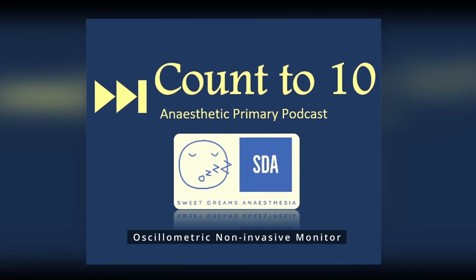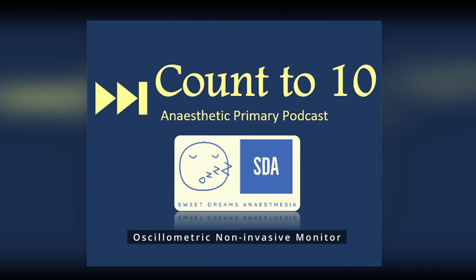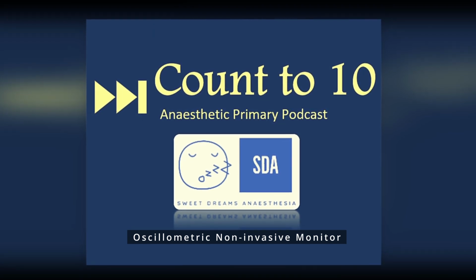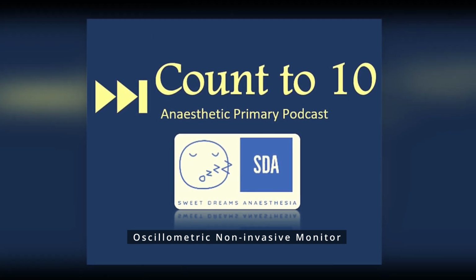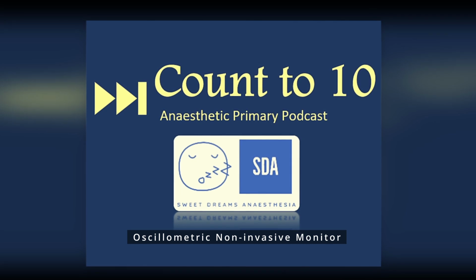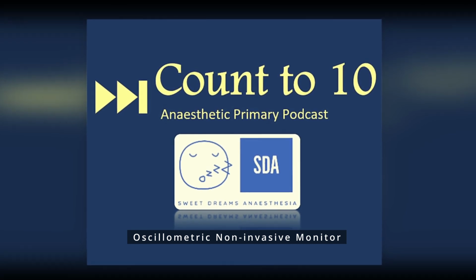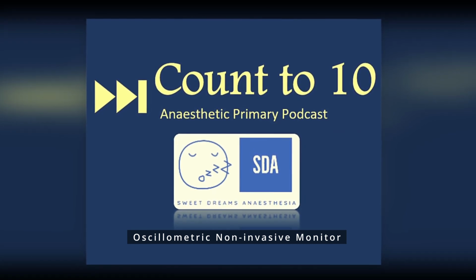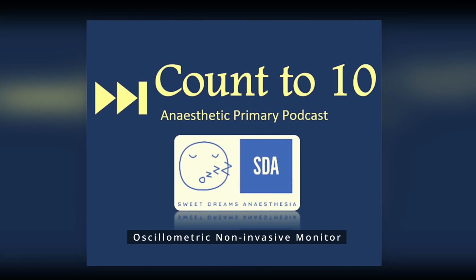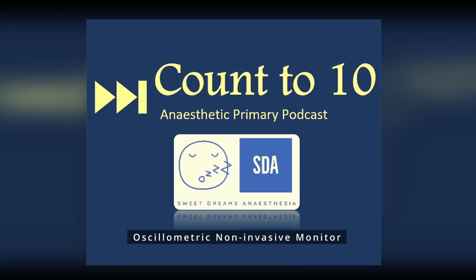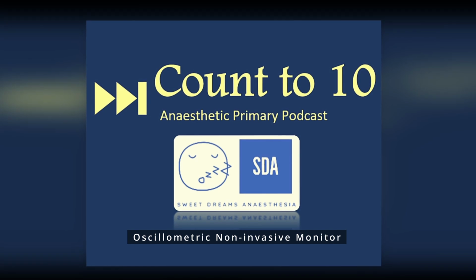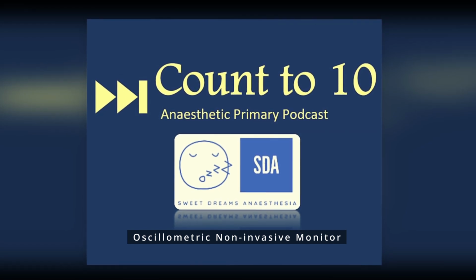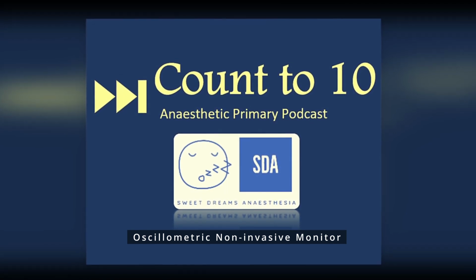The main advantage of using this automated oscillometric non-invasive blood pressure is that it's very easy, it's simple to apply, it's portable, it's versatile. It's what we use for all of our patients for our non-invasive blood pressure recording, not just intraoperatively, but post-operatively and on the ward. It's fast, and its most accurate reading is its mean arterial pressure.